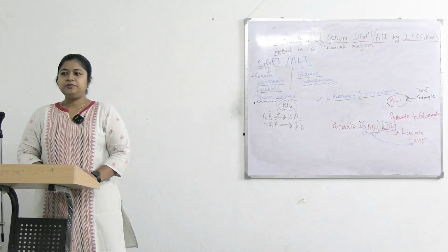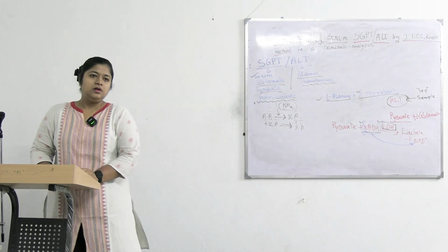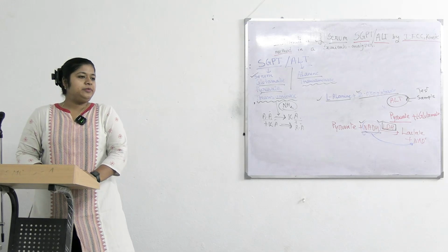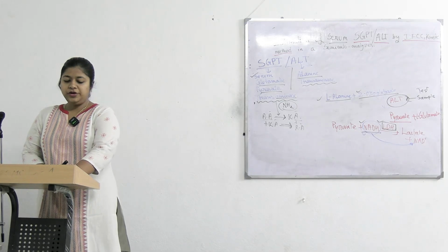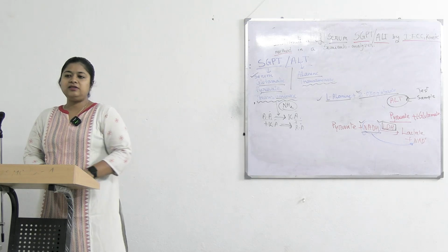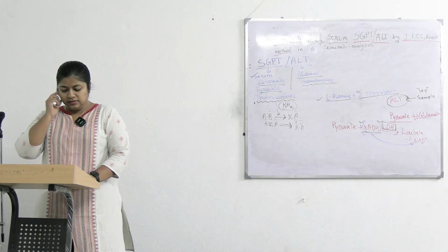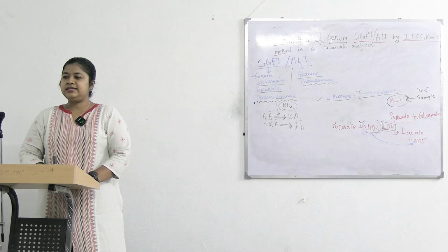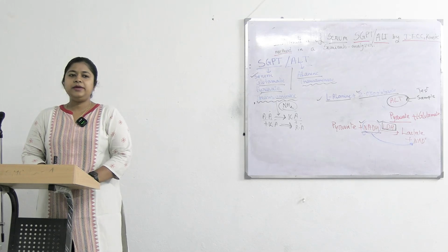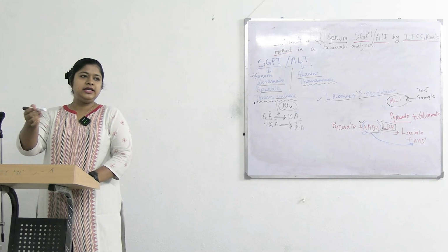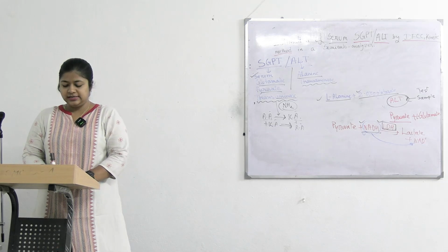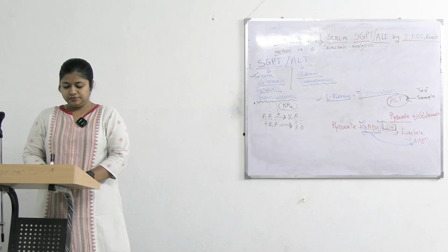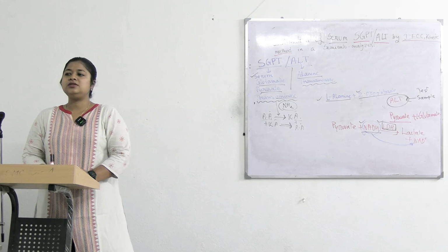So this is a kinetic method. What happens in kinetic method? Multiple readings are taken, or OD is estimated at different intervals. So here the lag time is 60 seconds. Lag time means after aspiration, first reading will be taken at 60 seconds. So write down, lag time is 60 seconds. Interval is also 60 seconds.